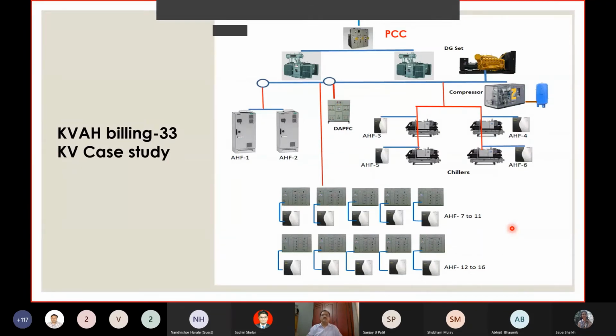Now I am discussing one case study of a 33 kV facility in Andhra Pradesh where kVAH billing is there. So this is the 33 kV point of common coupling. There are two transformers, and this facility had very high harmonic, almost 18-19%, and the kVAH was much higher than the kWH. More importantly, the client called us after facing very high failure of the boards, PCBs. Almost they were spending about 50 lakhs for PCB failures, and they had 10 lines of equipment. Each line of equipment was managed through an MCC. So we're talking about 10 MCCs, 4 chillers, and the rest of the company with a big compressor also and a standby generator.